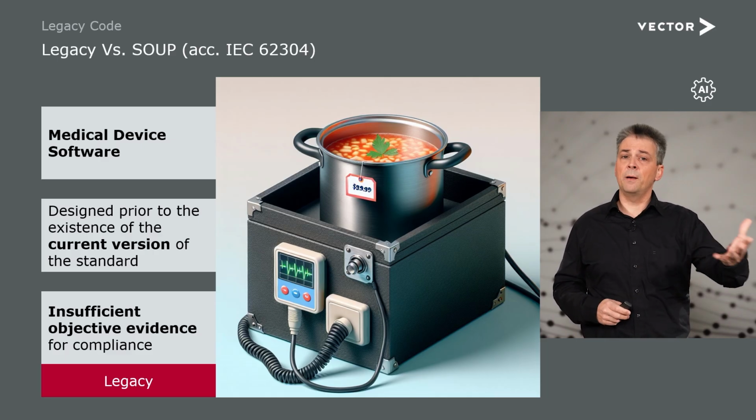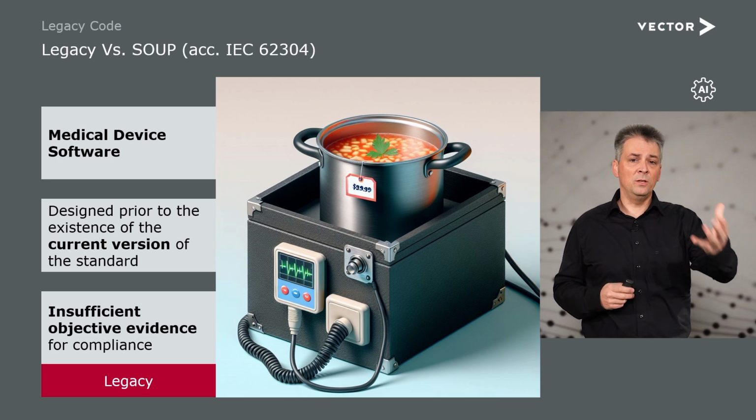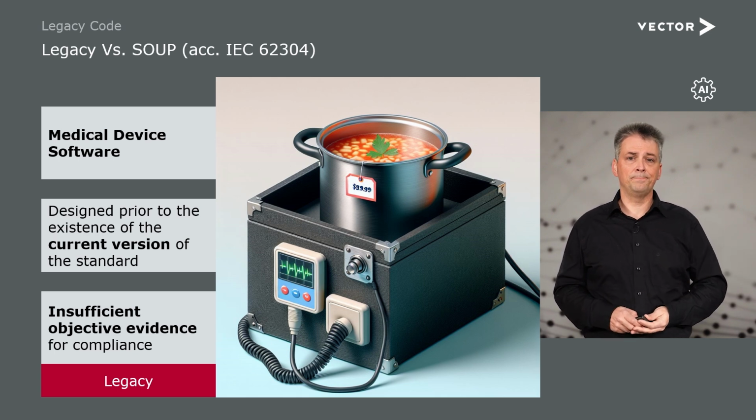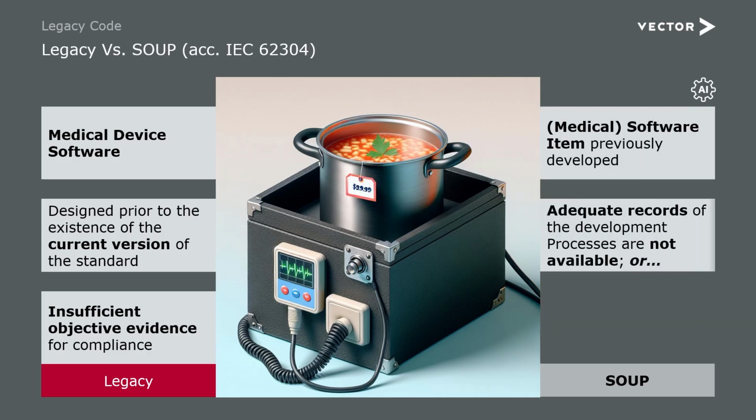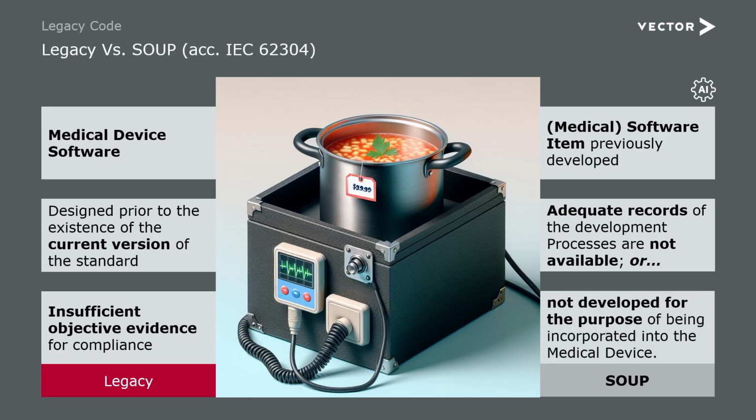So we already have some information in the use of this software in the medical market. On the other hand, the software of unknown provenance, the SOUP, is a software item that was previously developed. If it had been developed for medical, adequate records of the development processes are not available, or it was not developed for the purpose of being incorporated into the medical device. There was one side note concerning SOUP. The whole software system, the whole medical device software, cannot be declared as SOUP.